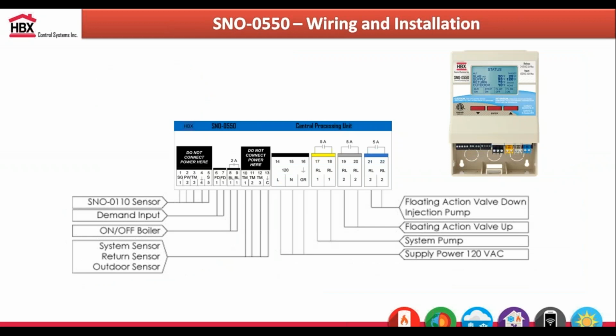In terms of new installs, when you're firing it up for your first snow melt, when it gets cold out for the first time, it usually takes about half an hour for the sensor to acclimatize. So if you get a wonky reading on that very first cold day, it's just the sensor acclimatizing. After about half an hour to an hour, depending on how cold it is, it will acclimatize and give you a normal temperature reading within your slab.